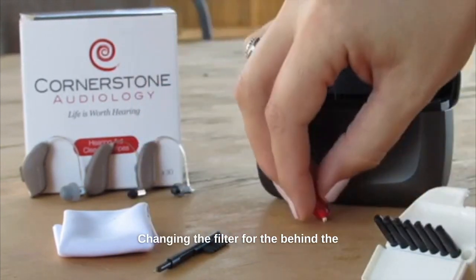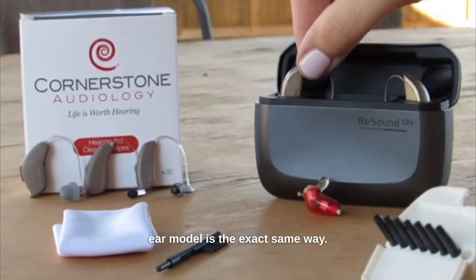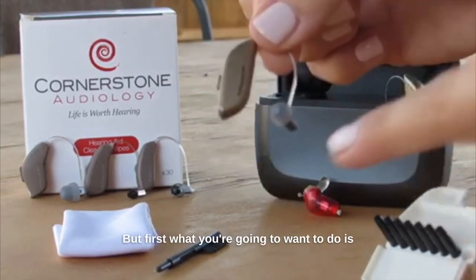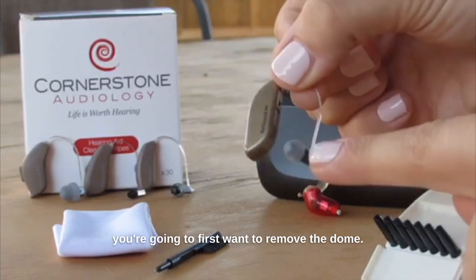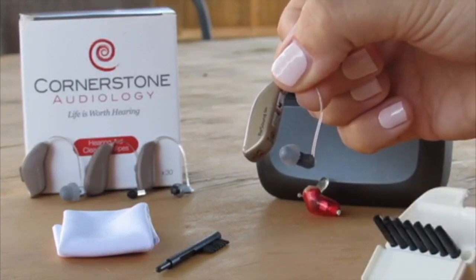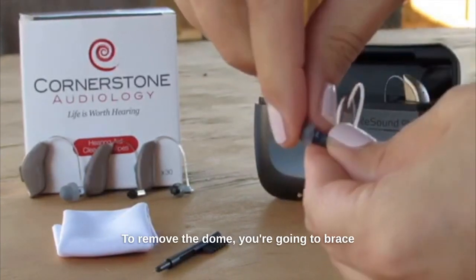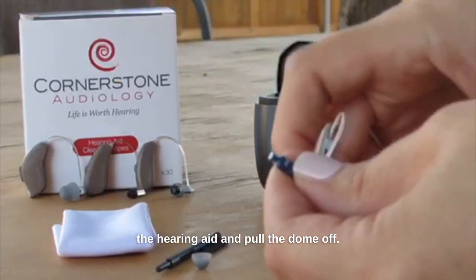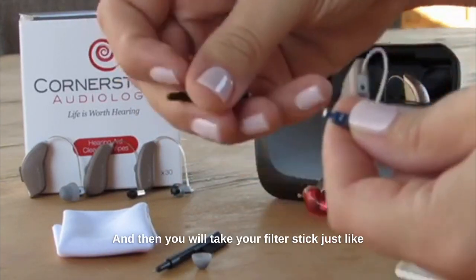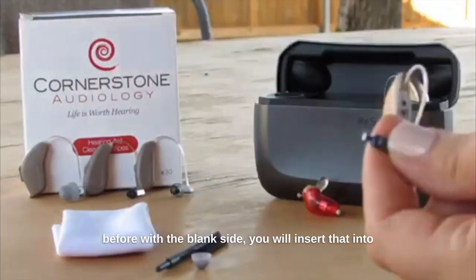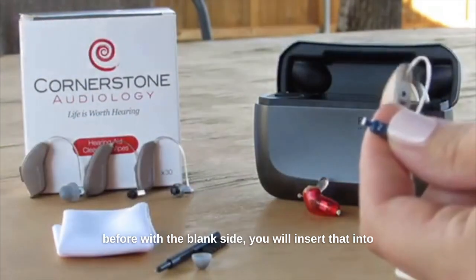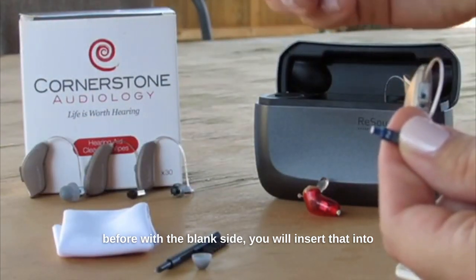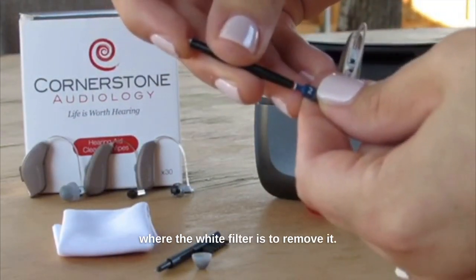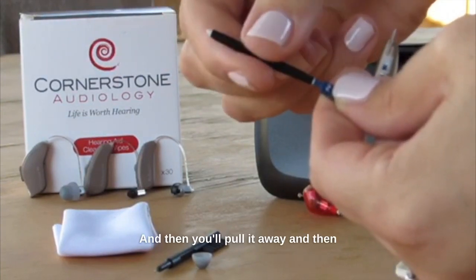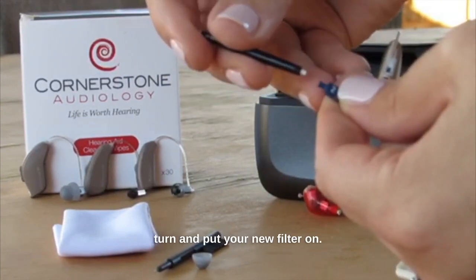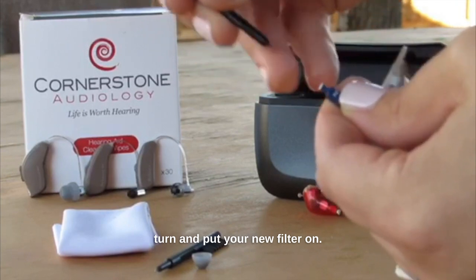Changing the filter for the behind the ear model is the exact same way, but first you're going to want to remove the dome. To remove the dome, you're going to brace the hearing aid and pull the dome off, and then you will take your filter stick just like before. With the blank side, you will insert that into where the white filter is to remove it. And then you'll pull it away and then turn and put your new filter on.